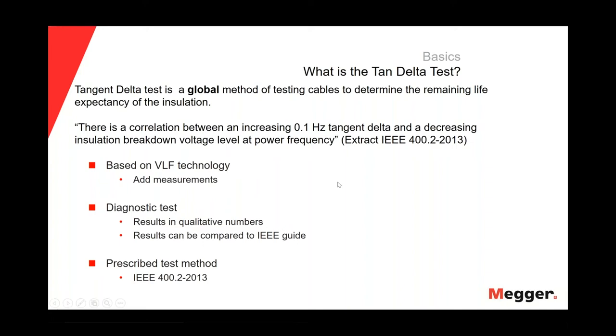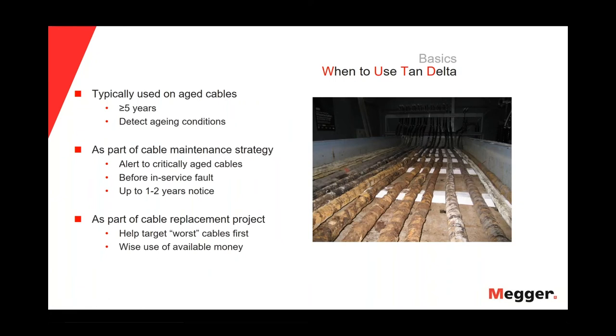So when to use the tan delta? Well, typically we would use the tan delta on aged cables at least 5 years old. The idea is to detect the aging conditions in the insulation of the cable. We can use the tan delta as part of a cable maintenance strategy to alert us to critical aged cables before in-service faults, with up to 1 or 2 years notice.